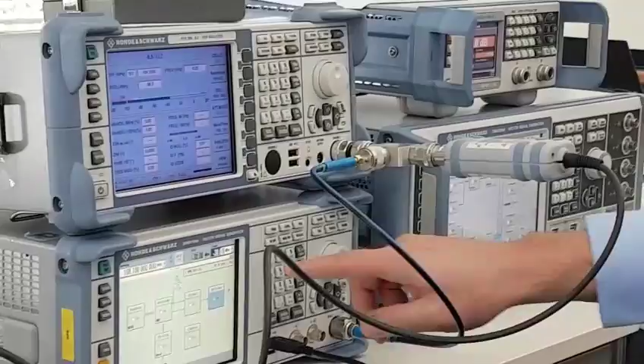And this is, let's say, our reference. And we'll check the hardware. Let's connect, okay, it reads the software version, and depending on the software version of the instrument, some tests are not available. For example, it checks the options, and it checks also the autocal status, so this is the self-alignment, so if this is still valid, then we will do this.